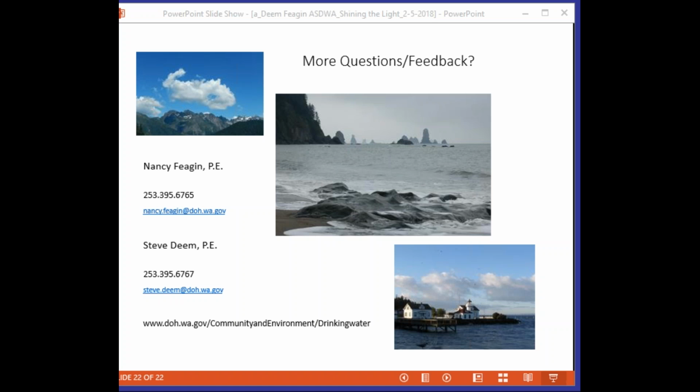Yeah, that's excellent. So Steve, I had a question last week. One of the state parks operators called me and he said, hey, I attended the disinfection webinar. It was great, but you said something that I have some concerns about, and it was about the secondary standard, the spec check that Hach makes for the Pocket Colorimeter 2.